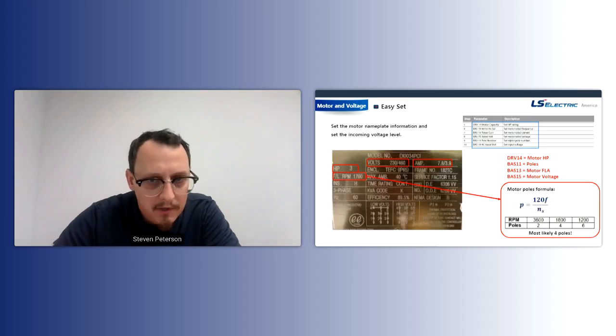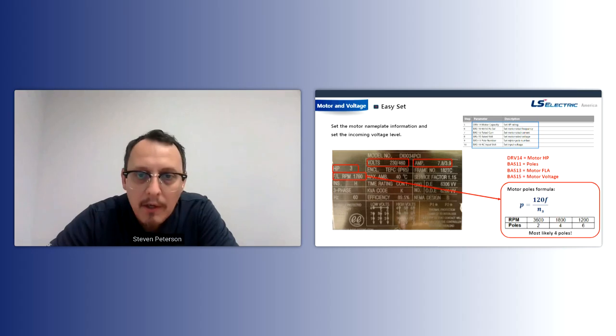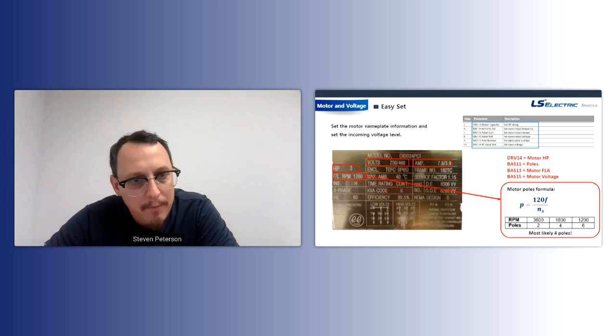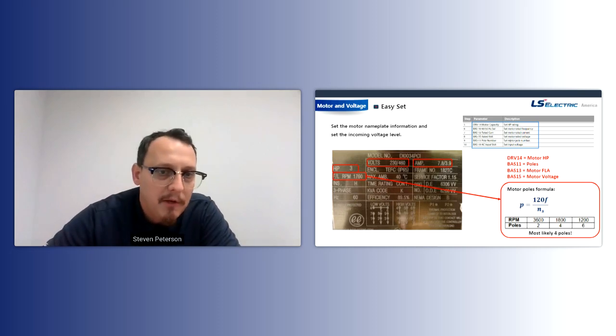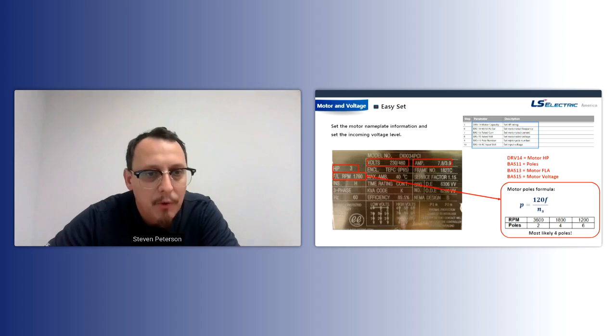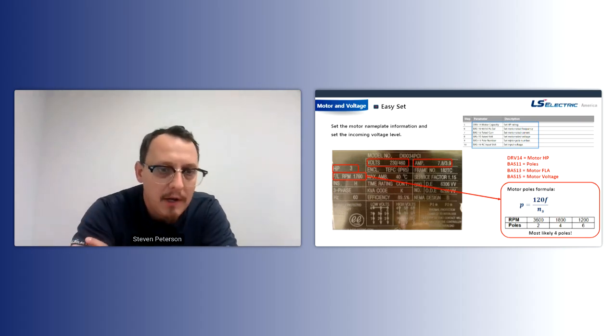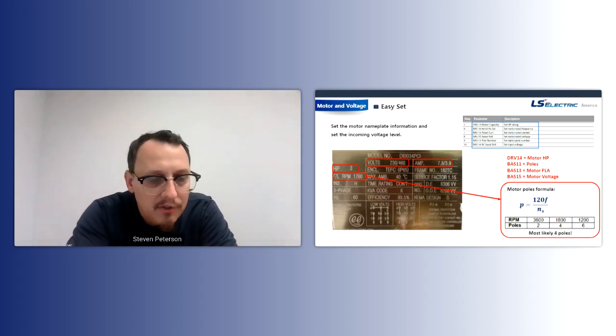Okay, so going on down the menu, we're on to the second group here, which is all motor related stuff as well as incoming voltage. So when you're setting up your motor parameters, we recommend either taking a picture or having another guy look at the motor nameplate and tell you everything. Okay, so here's a blown up picture of a motor nameplate. In this example, we have a 3 horsepower motor. So on the top left, that's the first thing you're going to enter: motor capacity and horsepower.